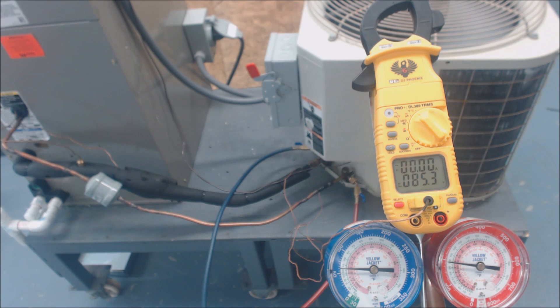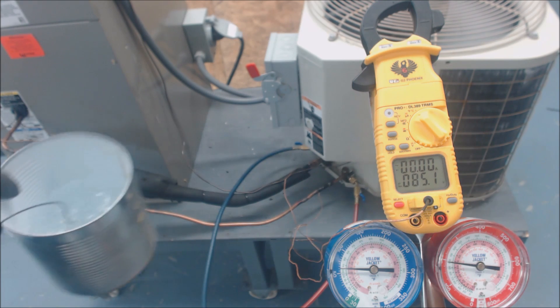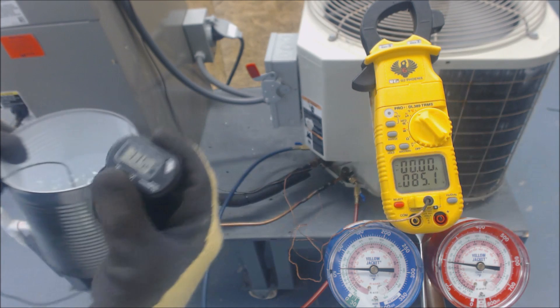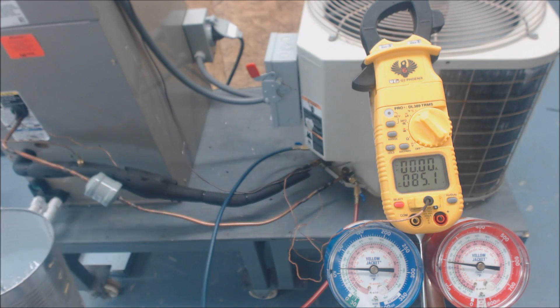We're going to give an indication of a bad TXV using low temperature. We're going to be sticking the TXV bulb in a cup of ice water. Presently the ice water is at 33 degrees.